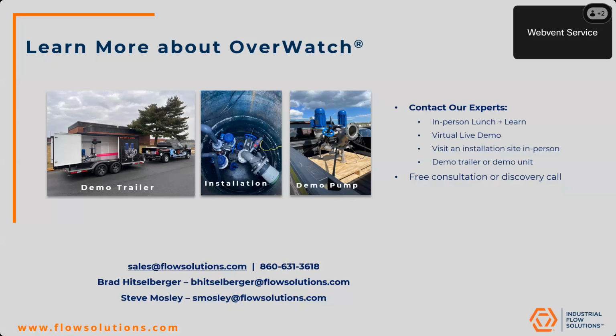What is the biggest size unit that you currently have done in the United States? Yeah, so we've done a couple units. We go up to about 200 horsepower for our biggest motor, and then 5,000 gallons per minute per one side and one volute, and then 400 feet of head. But the biggest one in the States that we've done so far has a duty point a little over 3,000 gallons per minute at 204 feet of head. So I think it's 3,100 gallons per minute at 204 feet of head. A large master station down there in the southeast for a municipality. But overseas, they have some even bigger that they've done over there in France.